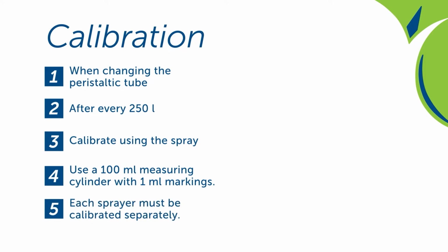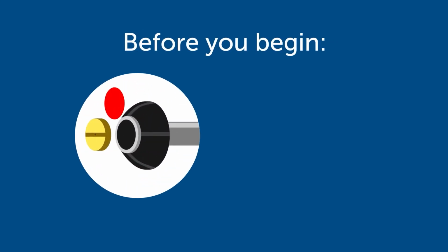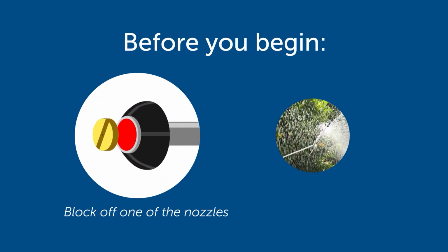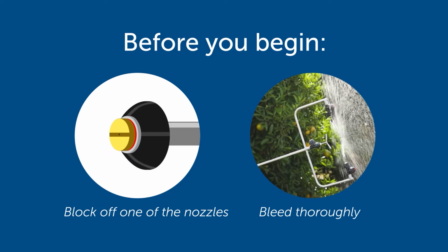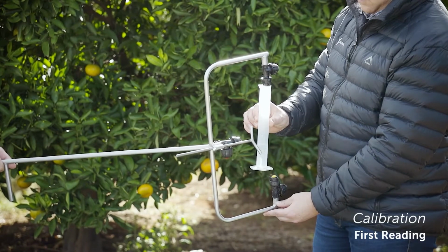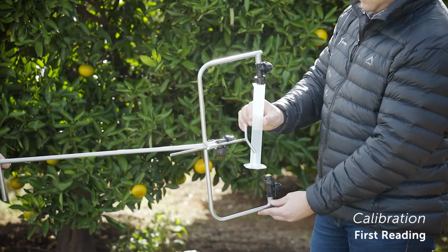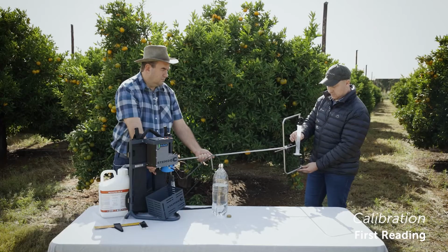Do the following to calibrate the sprayer. Block off one of the nozzles. Make sure the sprayer has been bled thoroughly. Hold the 100 milliliter measuring cylinder below the nozzle. Push and hold the on button until the pump stops automatically.